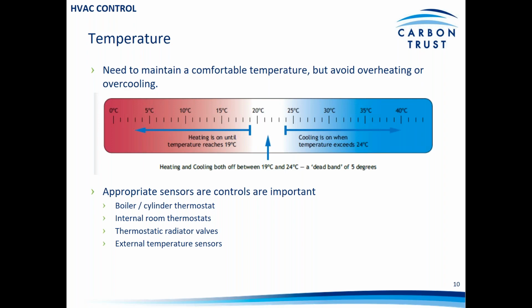Other sensors will be important in terms of boiler or cylinder thermostats. Also, the use of thermostatic radiator valves can be beneficial, just to allow manual control on individual rooms and to have them turned down to minimize the heat requirement in certain areas. And in addition, you can utilize external temperature sensors to compensate your system for external conditions. So that might mean that your heating system comes on earlier on particularly cold days, or if it's warming up outside, it gets the chance to switch off early as well.